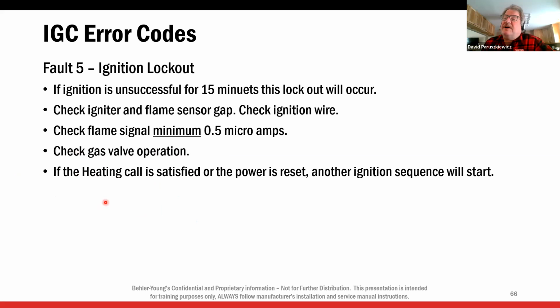Okay, fault 5, ignition lockout. Now, flame signal, we're going to talk about for a second, because it's actually fairly simple, and a lot of guys don't really understand it. So ignition lockout. If ignition is unsuccessful for 15 minutes, this lockout will occur. So if I've tried my 5-second ignition periods, 22-second waits, up to 15 minutes, we're going to lock out.